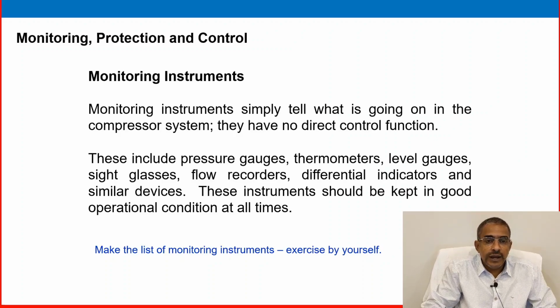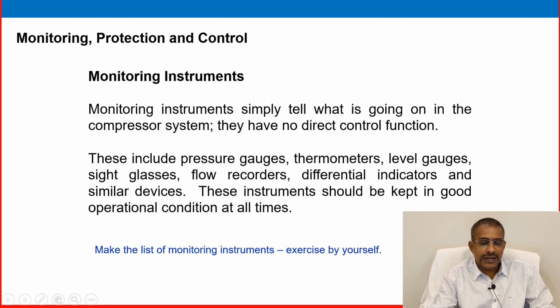So that's why a lot of instruments and other systems are provided to maintain compressor protection. Let us see how it works. Monitoring instruments simply tell what is going on in the compressor system. They have no direct control function. These include pressure gauges, thermometers, level gauges, sight glasses, flow recorders, differential indicators and similar devices.